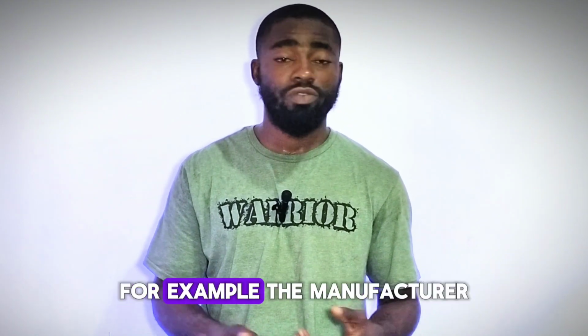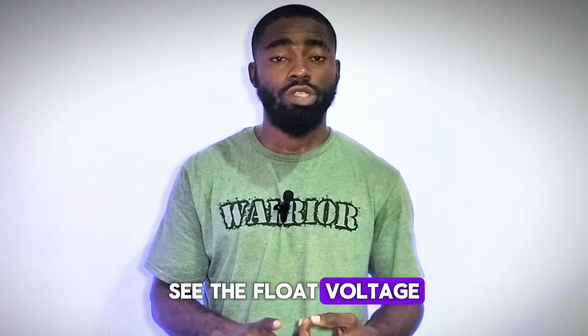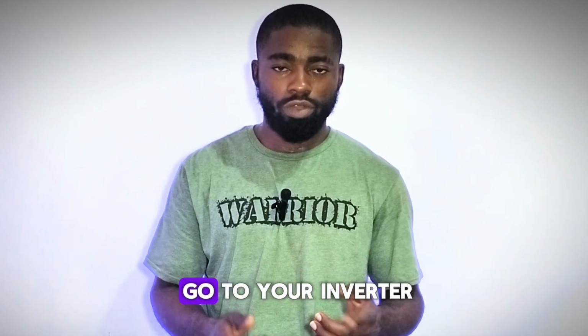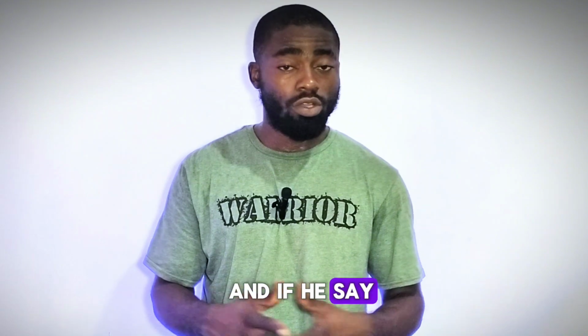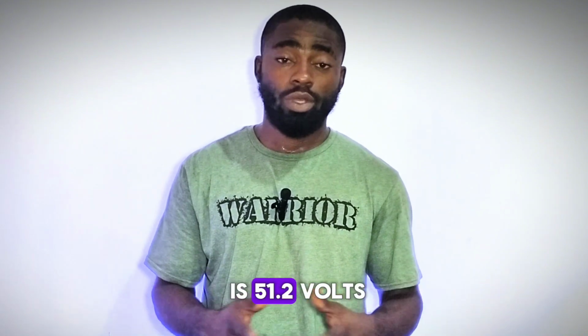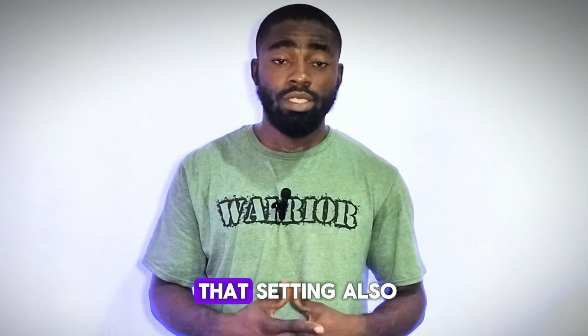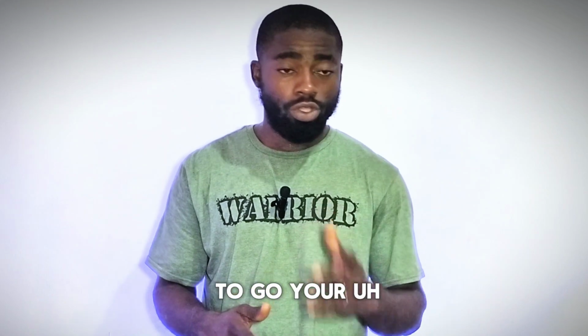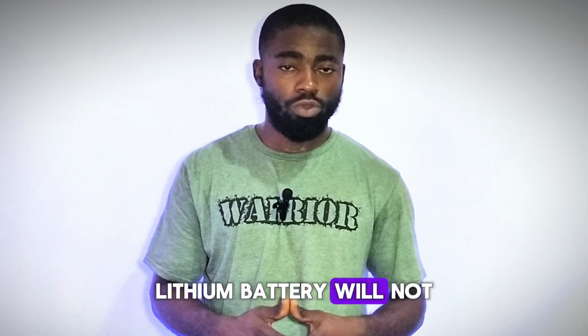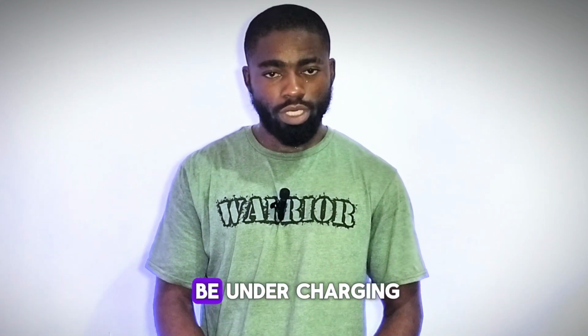For example, if the manufacturer says the float voltage or absorb voltage of the battery is 57.6, you would want to go to your inverter and do that setting. And if they say the low voltage disconnect is 51.2 volts, don't forget to do that setting also, and you are good to go. Your lithium battery will not be overcharging and it will not be undercharging.